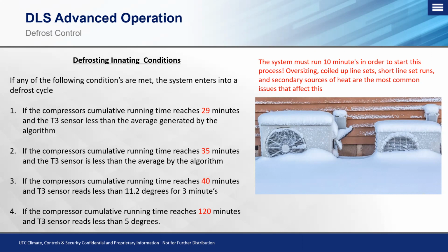Okay, the system doesn't realize that after the first heating cycle, if it ran 9 minutes, I only have 1 more minute to run on the next cycle before I go into a defrost. Okay, it restarts as soon as it's done. It doesn't realize that it ran 9 minutes on the previous cycle.